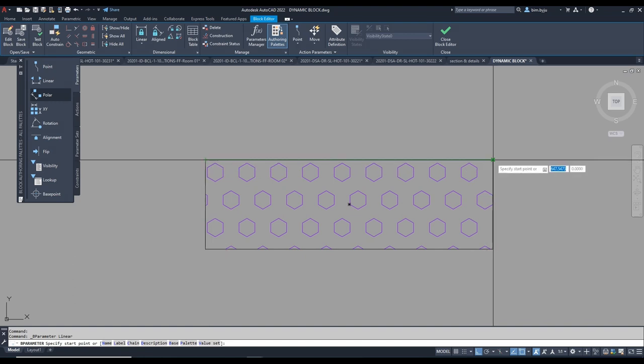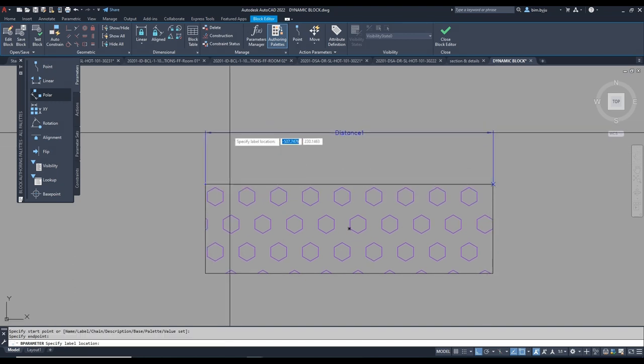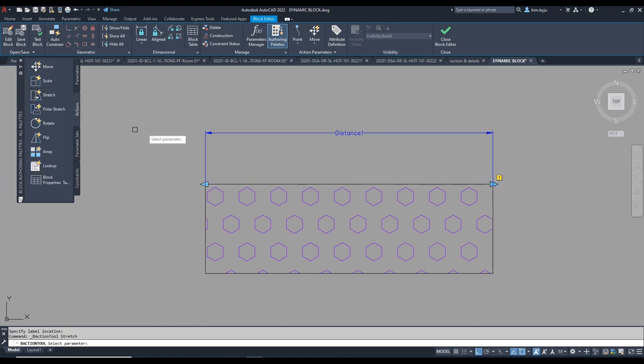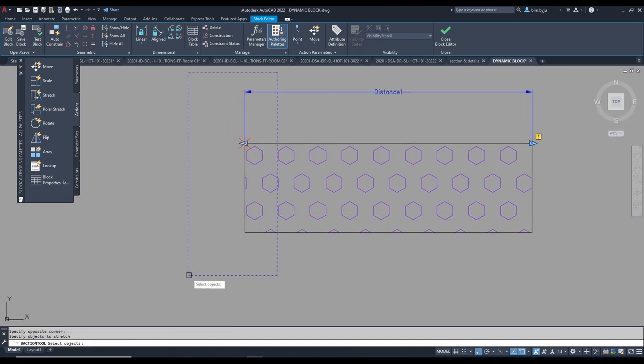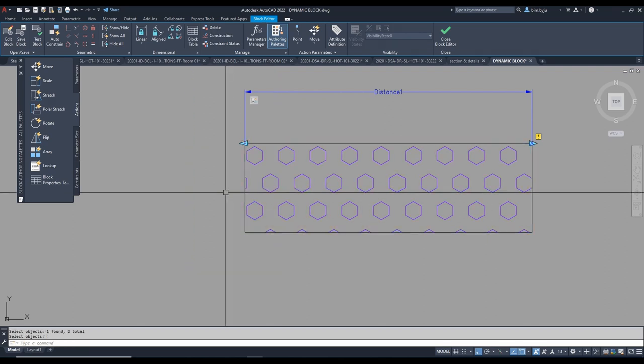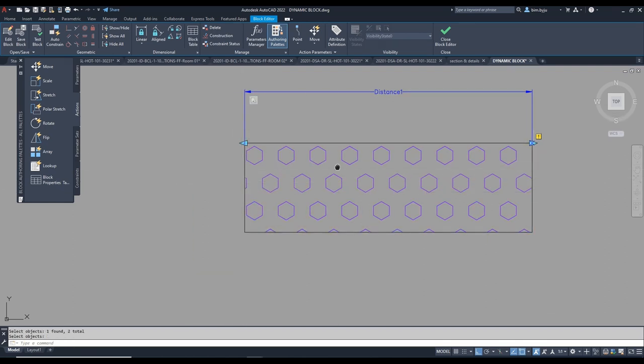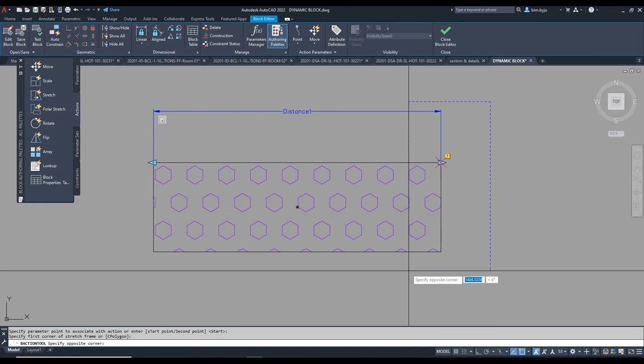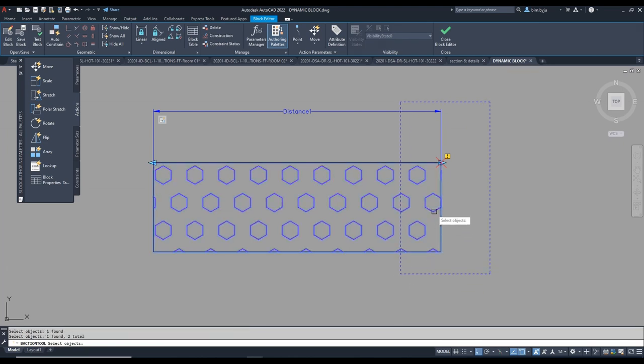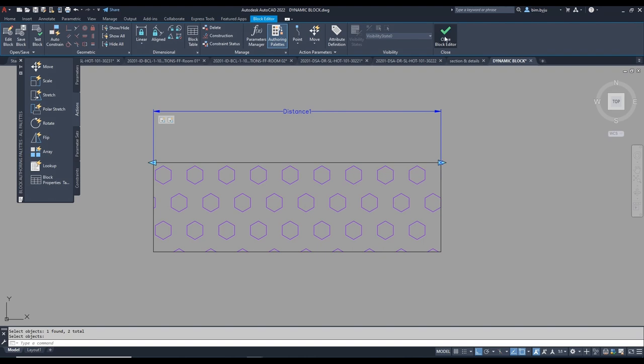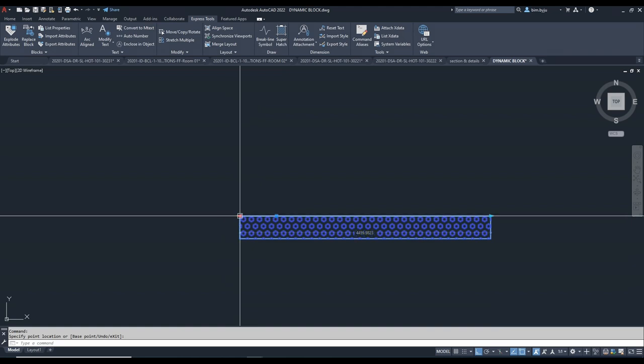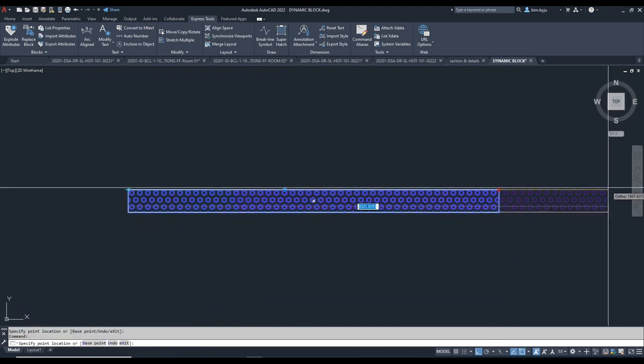In the block editor, I add a Linear parameter — Distance 1 — for stretching in two directions. I go to Actions, select Stretch, pick this point, drag the frame, then select the objects and press Enter. One stretch action is created. I create another Stretch action in the other direction, pick the point, drag, select the objects, and Enter. Then I save the block and we can see the 400mm cable tray stretching.